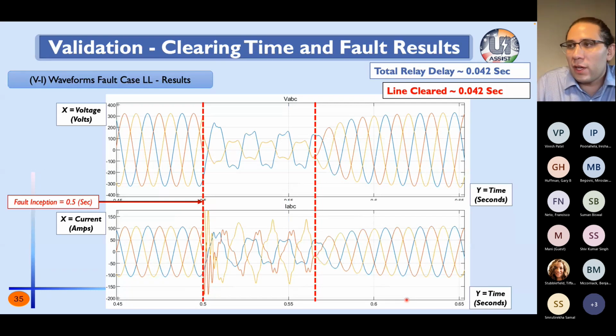Here I'm showing the effectiveness of this method with a test case of a fault and an auto trip of the relay. We have a fault at 0.5 seconds. In this case we tested a double line fault. I'm showing the voltage and the current. Once we have the fault, it goes through the algorithm and is detected. Then it goes through the communication lane, to the tripping signal, until it reaches the circuit breaker and is able to open the grid. We have this time gap, which is a faulty operation regime.